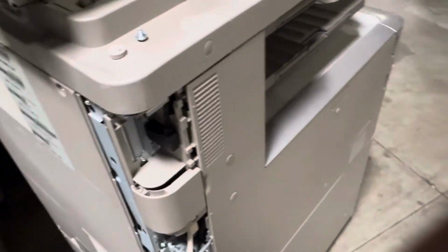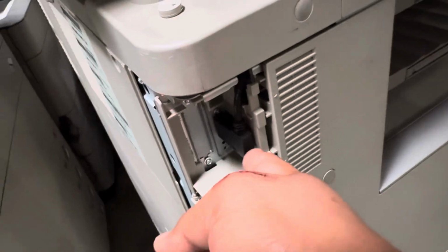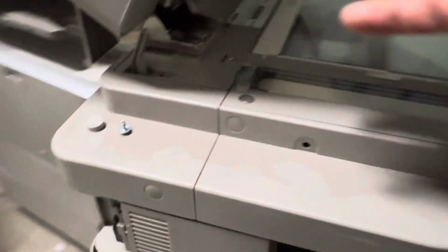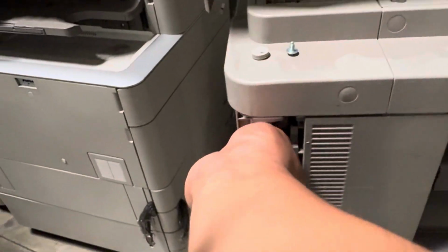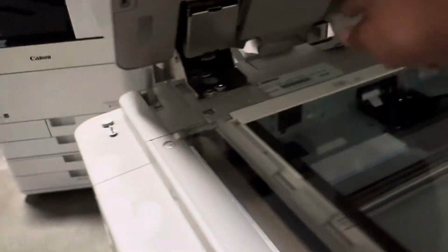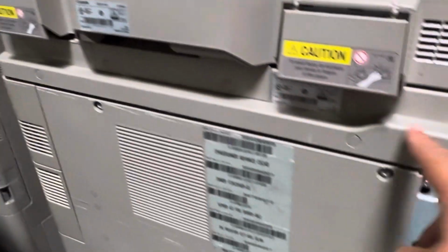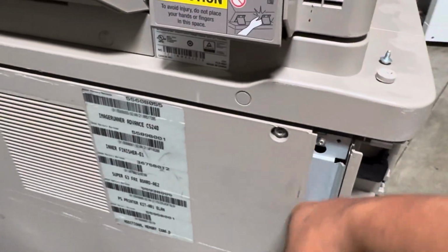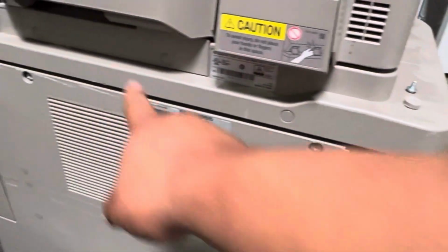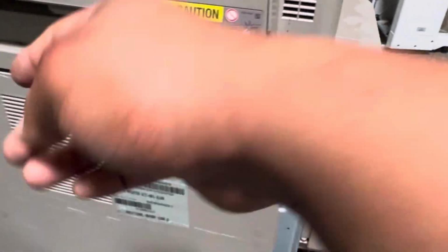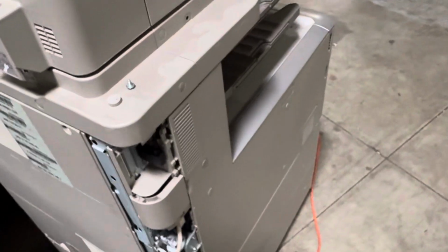And that's about it. Other than this board being bad, something's not communicating. You're getting the communication code, so you'll have to check this, because that communicates to the reader. The reader, of course, does all this and the feeder, and so this connection is not communicating with the main controller here. So it'll be this, or this wire here that you'll need to check, and that'll be it.